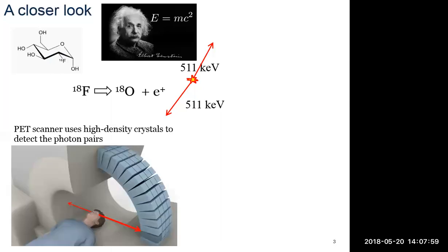We've injected that radiotracer, it transports through the body, hopefully also goes into the brain — fluorodeoxyglucose does. We'll be getting positrons being emitted from the F-18 FDG. We're seeing in this schematic a single pair of annihilation photons that have come about from a positron annihilating with an electron. We get those two back-to-back 511 keV photons, which are very energetic, and the PET scanner normally consists of relatively high-density crystals in order to stop and detect those high-energy photons.